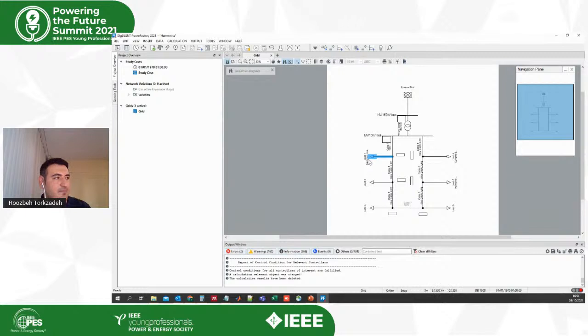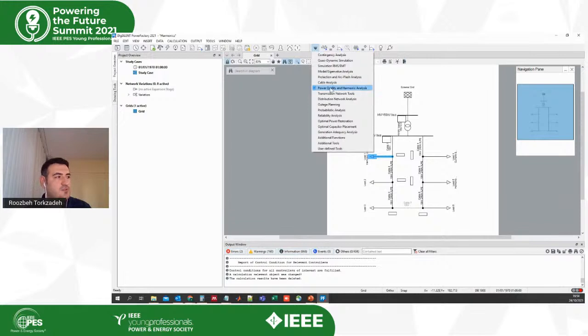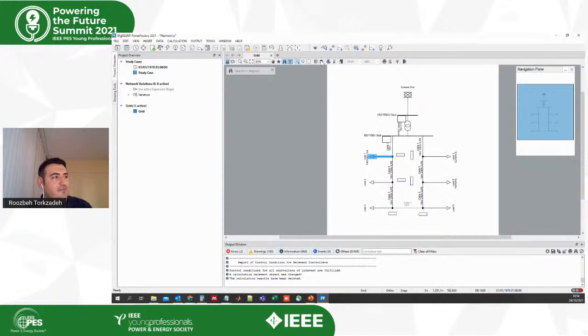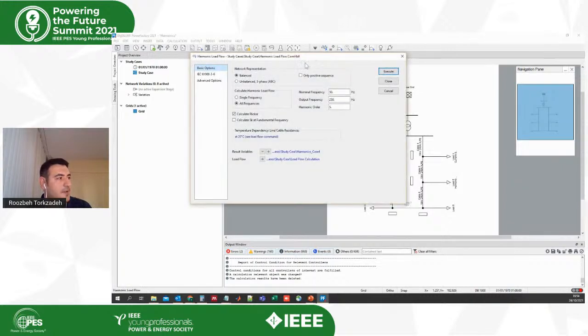To investigate the impacts, we need to run a harmonic load flow. So instead of doing a regular load flow, we need to run a harmonic load flow. For doing that, from this drop-down menu, we need to select Power Quality and Harmonic Analysis. And here we have different analysis types. The first one is Calculate Harmonic Load Flow. In this one, you can go for balanced or unbalanced network. Here we have a balanced harmonic source, so I will select the first one.